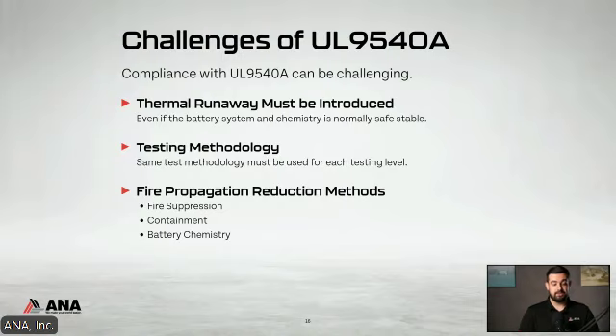Fire propagation reduction methods. Again, based on your fire propagation testing, you may need to incorporate additional fire propagation reduction methods such as fire suppression, whether it's a foam or some other kind of cooling, whether it's changing your enclosure to contain the fire, or you may even need to change your battery chemistry in general.